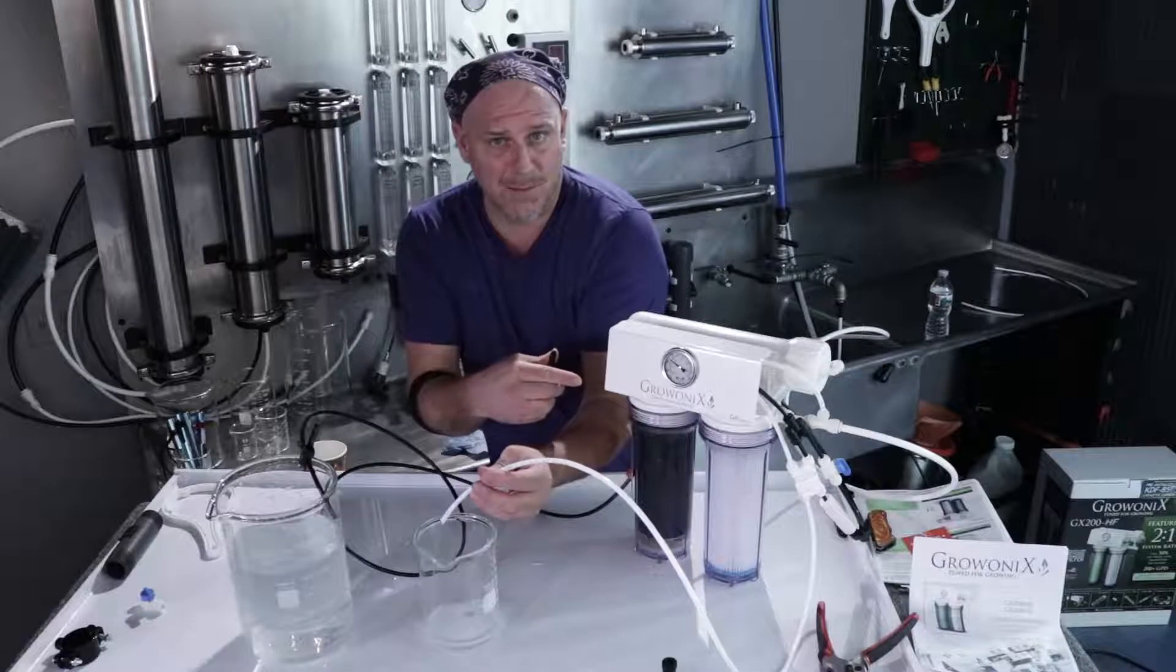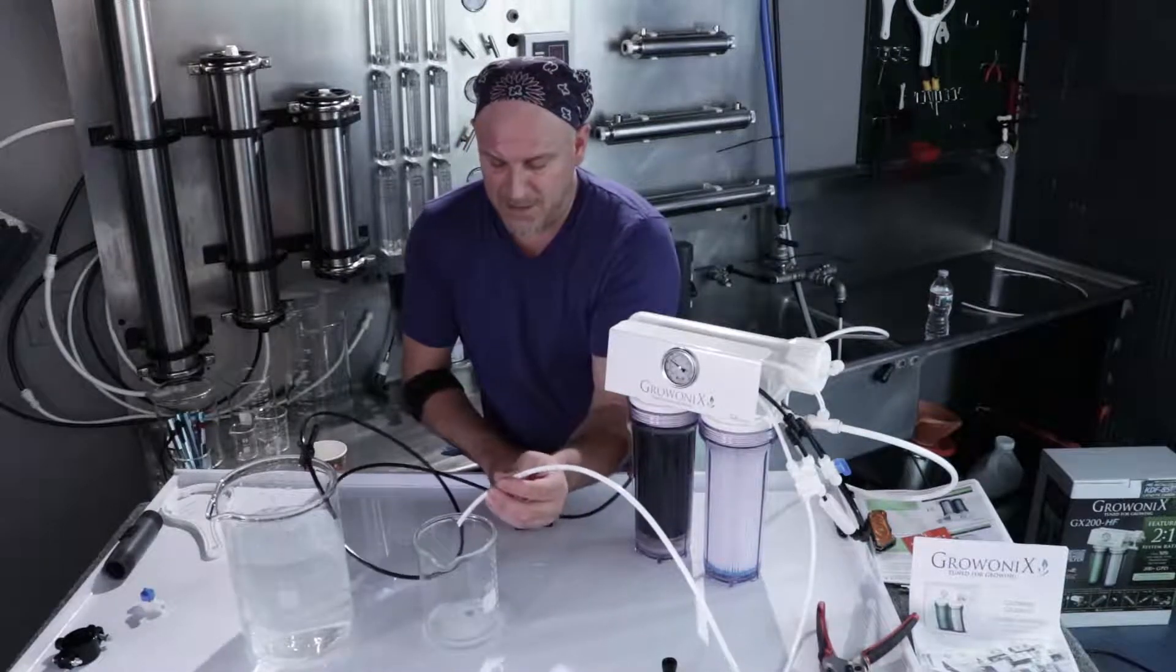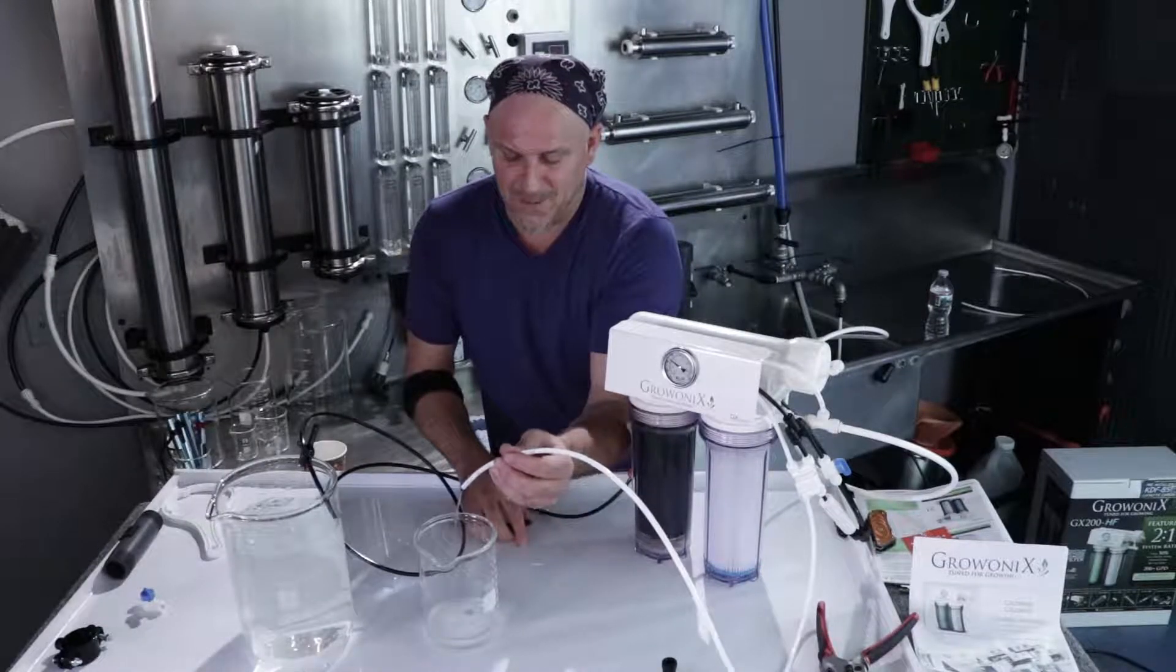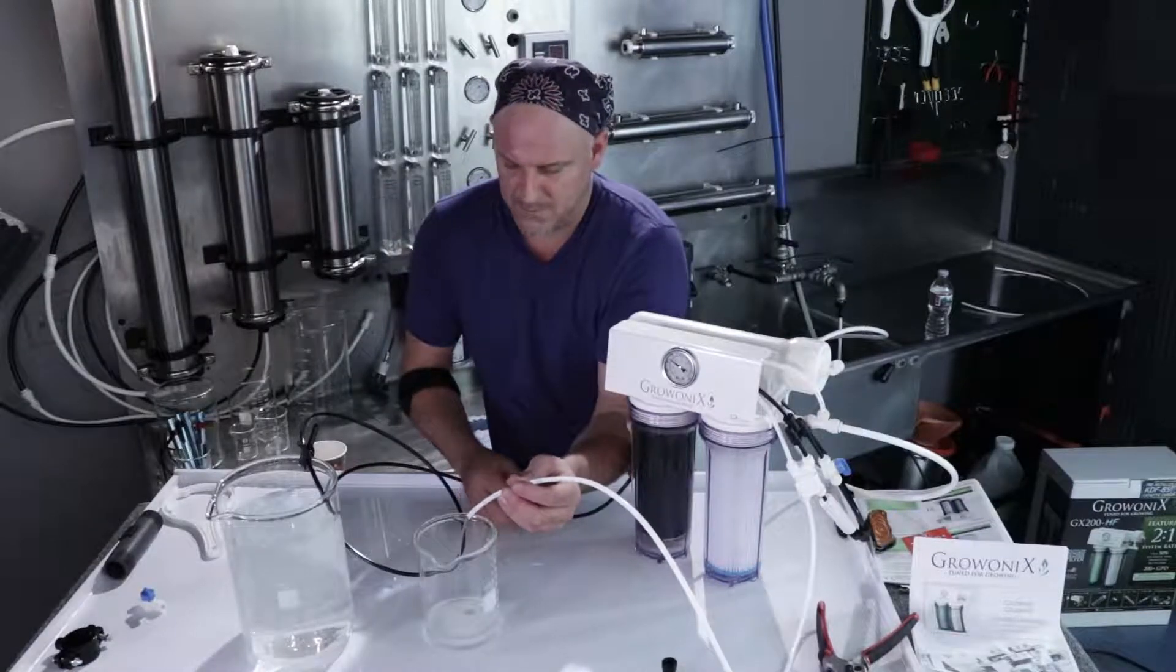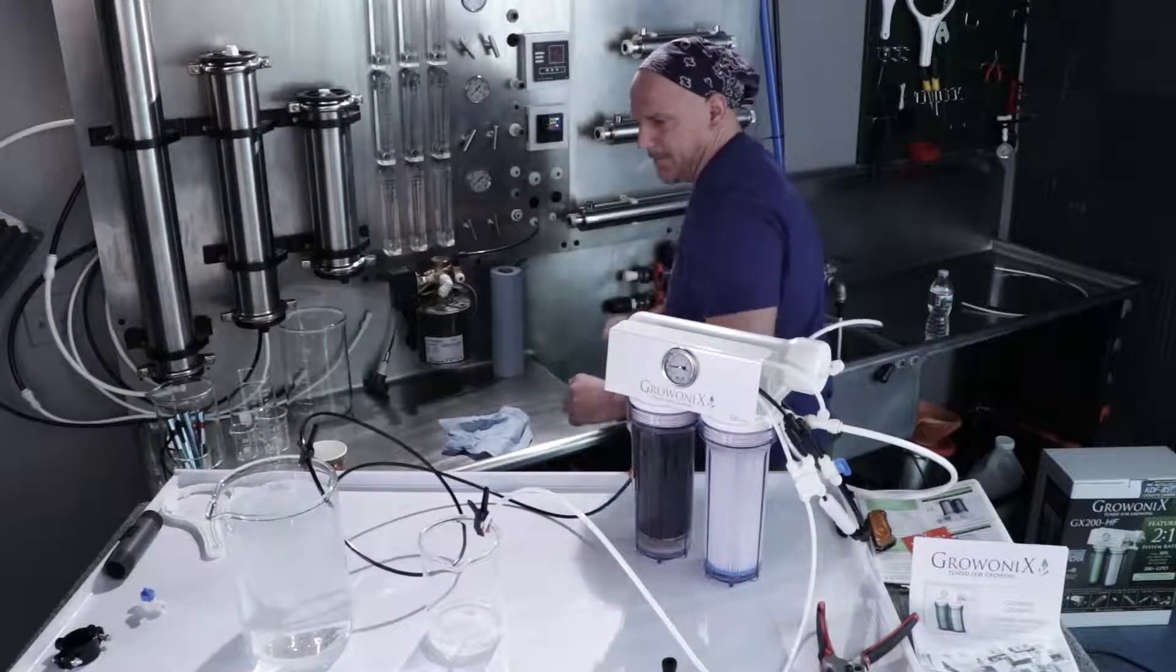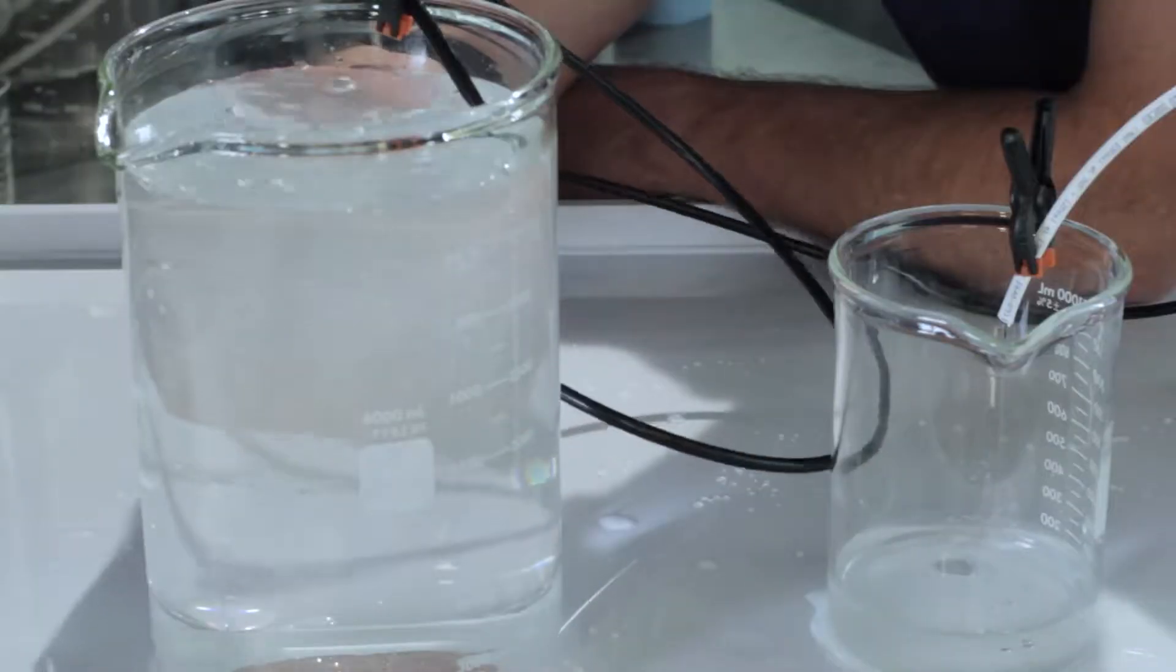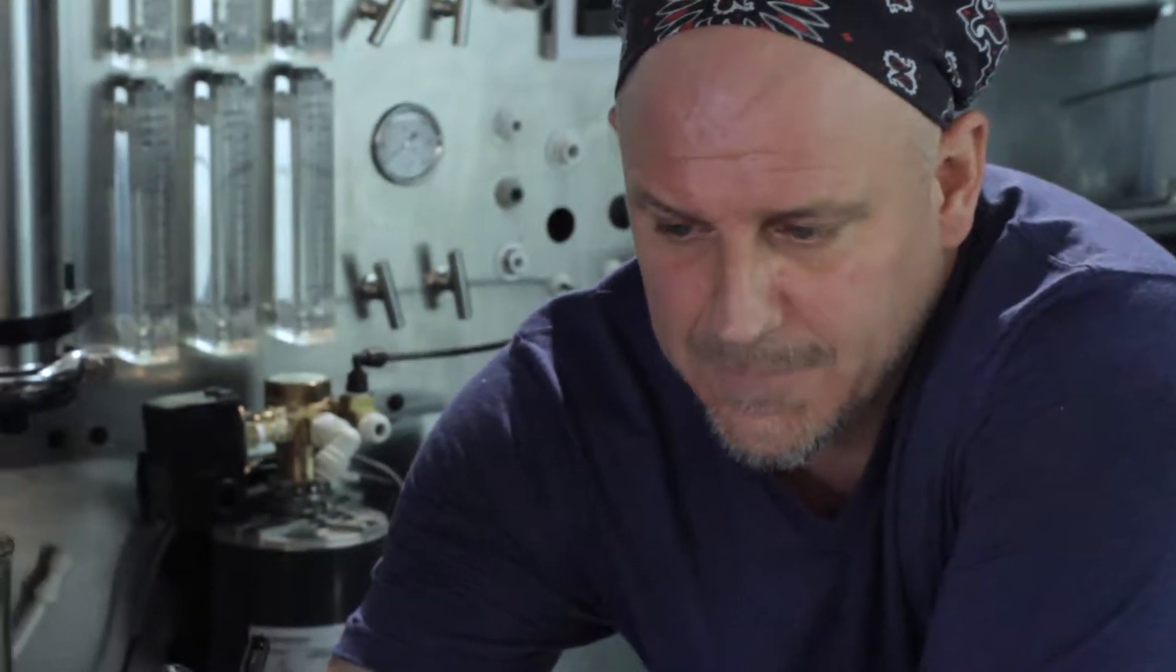Even though the flush valve is open, reverse osmosis is happening and we're making some permeate water. Generally you want to take the first 20 gallons of permeate water and just discard it. You'll notice if you look at the drain water, it's not completely translucent like clear water, it's a little bit yellowish, and that is the storage solution in it.